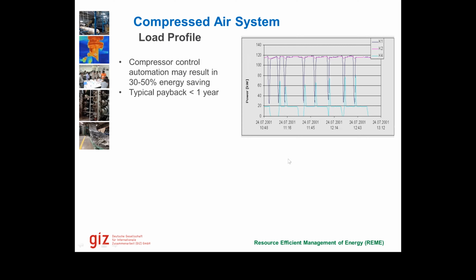Do you see this chart? As you can see, the moment compressor K1 goes off load, the compressor K4 goes on load. And the moment compressor K1 reaches its maximum load, the K4 goes into offload position. But the main issue here is that the moment this K1 goes into offload position, the K4 starts kicking in. But as soon as K4 is at its peak, K1 starts to kick in and K4 has to go down. So you can see that K1 is going into reasonable load here, then going off load, but K4 is only going into load for a fraction of time and then going off load.